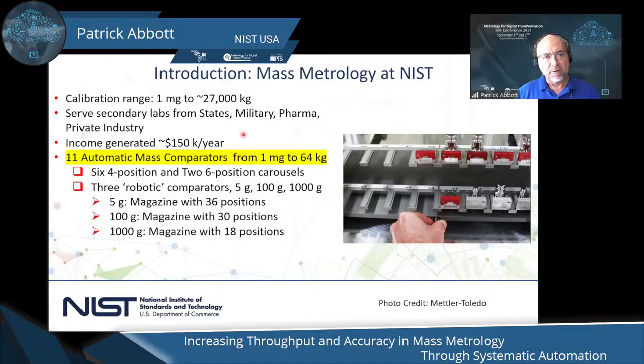More to the point, in our laboratories, we have 11 automatic mass comparators that range from 6 grams to 64 kilograms. It has a limitation, a resolution of 1 milligram, I should say. Among those 11 instruments, there are 6 4-position and 2 6-position carousel instruments. I'll show you that in a minute. And there are 3 robotic mass comparators of the type that I showed you in my introductory slide.